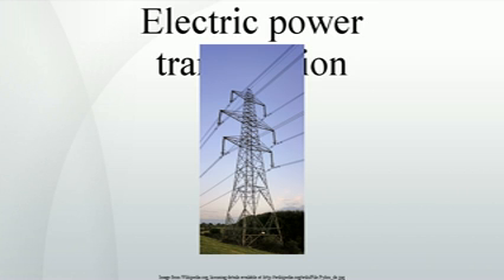While subtransmission circuits are usually carried on overhead lines, in urban areas buried cable may be used. There is no fixed cutoff between subtransmission and transmission, or subtransmission and distribution. The voltage ranges overlap somewhat. Voltages of 69 kV, 115 kV and 138 kV are often used for subtransmission in North America. As power systems evolved, voltages formerly used for transmission were used for subtransmission, and subtransmission voltages became distribution voltages. Like transmission, subtransmission moves relatively large amounts of power, and like distribution, subtransmission covers an area instead of just point-to-point.